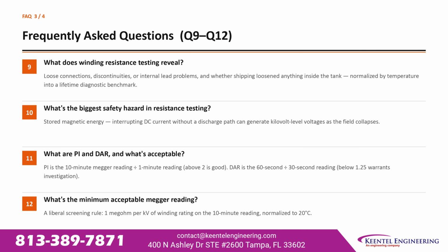What does winding resistance testing reveal? Loose connections, discontinuities, or internal lead problems, and whether shipping loosened anything inside the tank, normalized by temperature into a lifetime diagnostic benchmark. What's the biggest safety hazard in resistance testing? Stored magnetic energy. Interrupting DC current without a discharge path can generate kilovolt-level voltages as the field collapses.